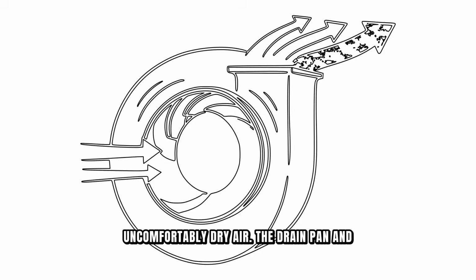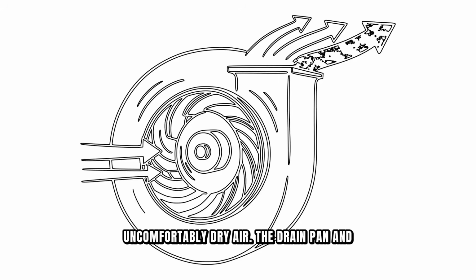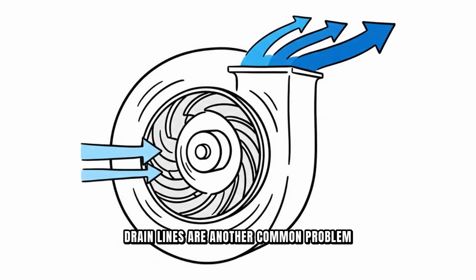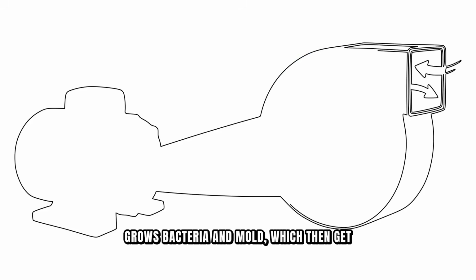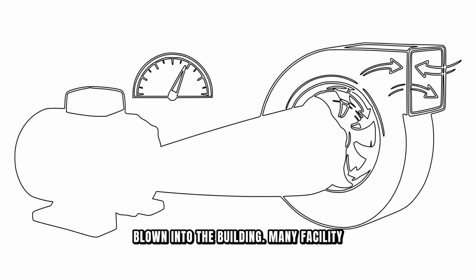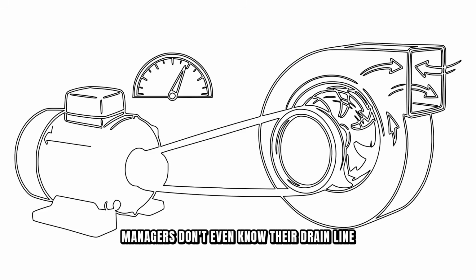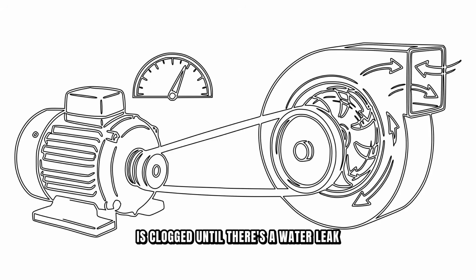The drain pan and drain lines are another common problem area. If that drain line clogs, water backs up in the pan and becomes stagnant. Stagnant water grows bacteria and mold, which then get blown into the building. Many facility managers don't even know their drain line is clogged until there's a water leak or health complaints start.